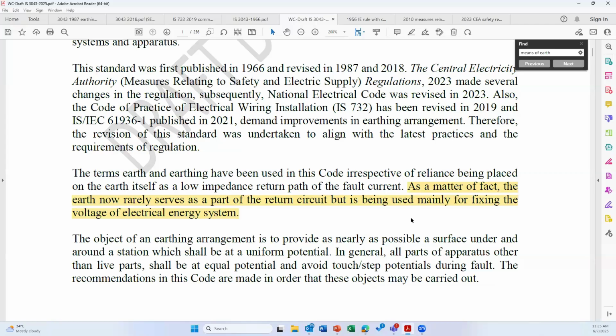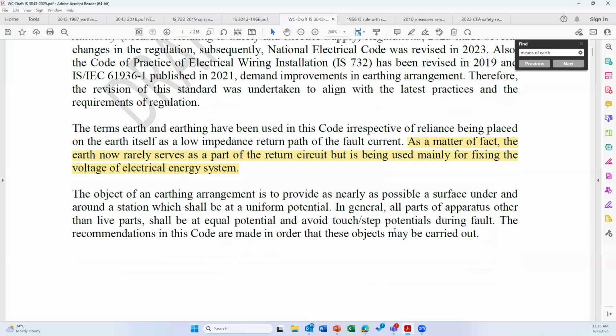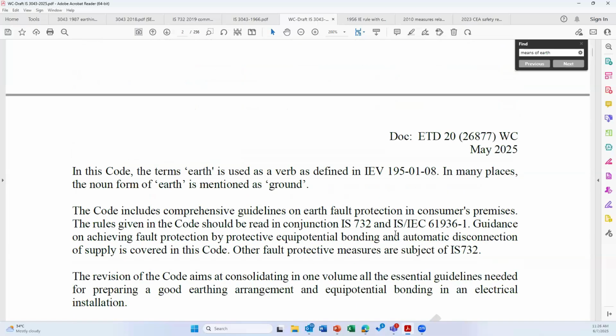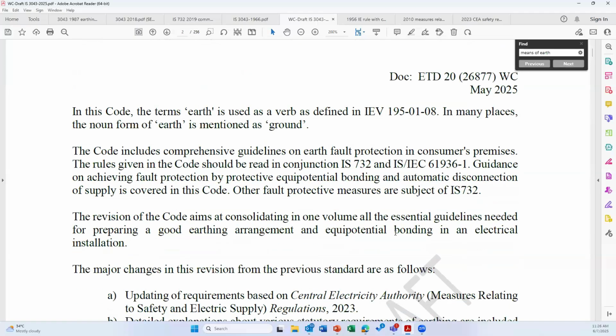This is absolutely wrong. In an actual scenario, the fault current in a low voltage system, let's say for a TT system, the current through the earth electrode may be a few amps, maybe 100 amps, 200 amps, 300 amps, never more than that. So 50 kiloampere or 25 kiloampere current flowing through an earth electrode in a low voltage system, or even in a system up to 11 kV, 22 kV, 33 kV, is not correct. So this time, a lot of improvement has been made in IS 3043.